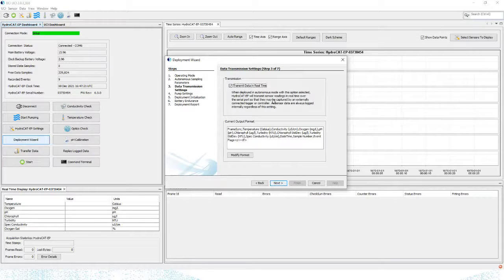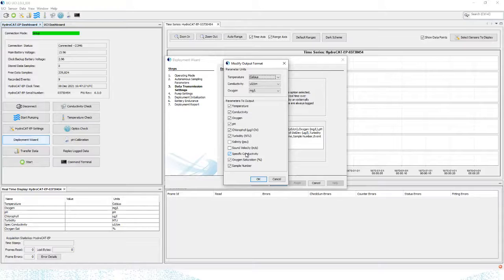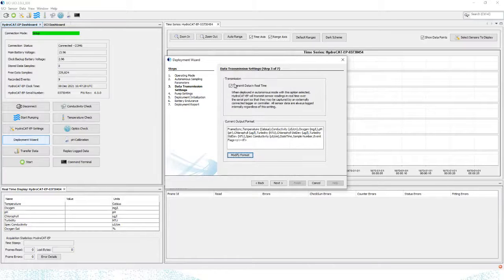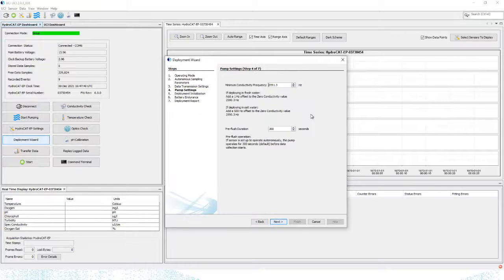And then I can change settings similar to what we saw in the HydroCAT EP settings. I can configure it to transmit data in real time, and change my output format just as we did before. In this case, say I'm deploying this only sampling data on the instrument memory, so I want to turn this off because I want to save a little bit of power and I'm not sending data to a data logger.